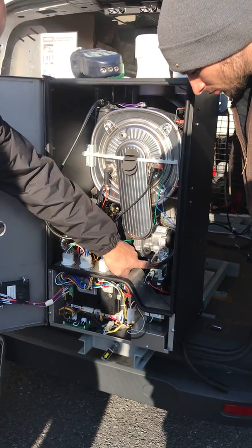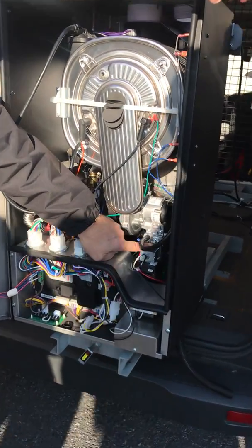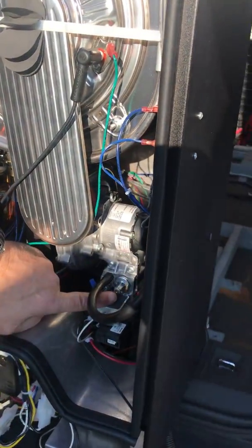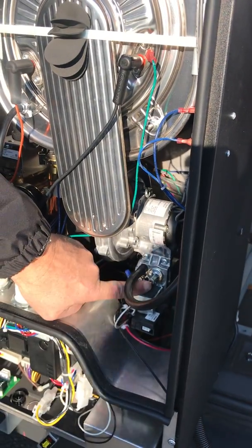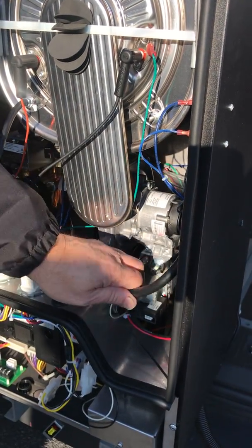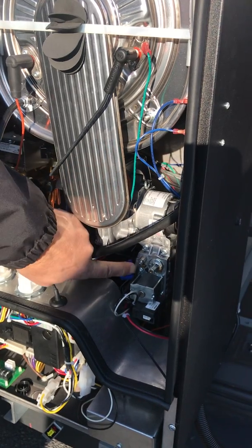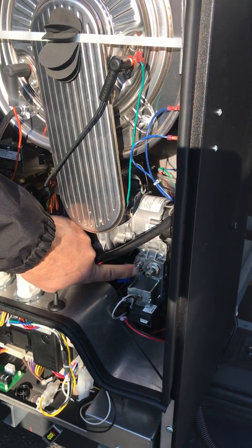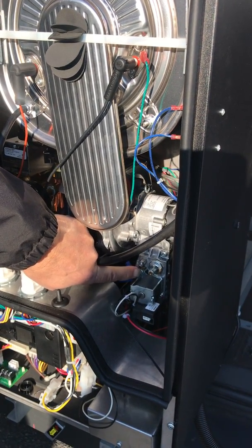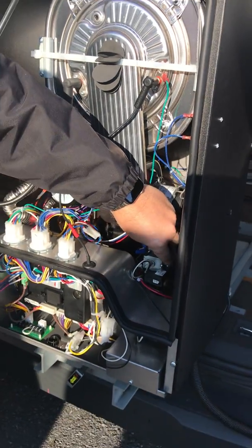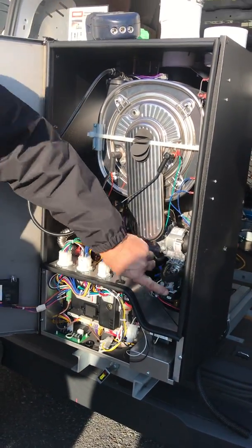This little raised portion here, there's a 2mm Allen wrench. That is the low fire adjustment. And down underneath here, there's a little throttle screw, that's the high fire adjustment. I'll go through that upstairs, but there are 2 adjustments on this gas valve.